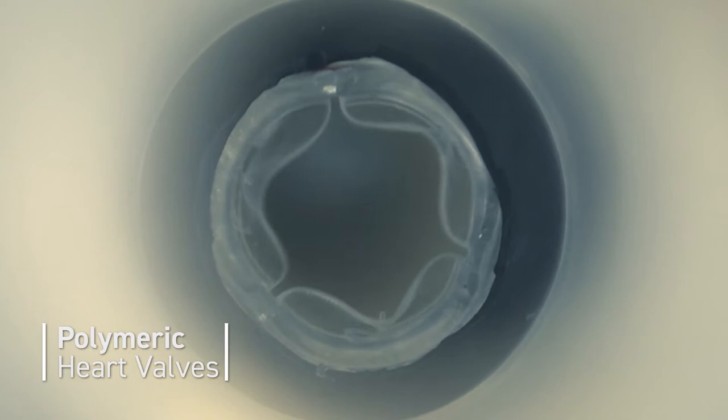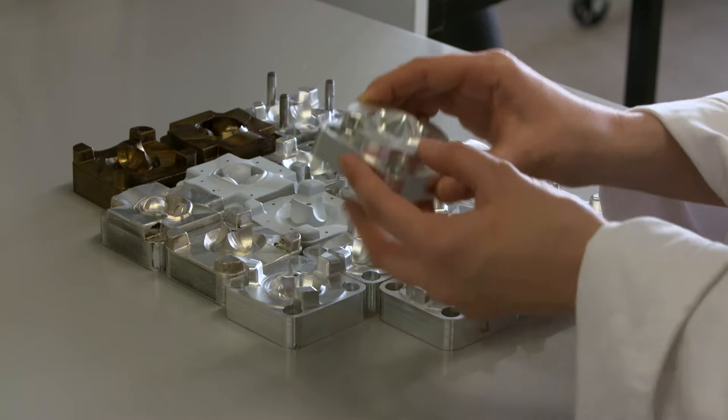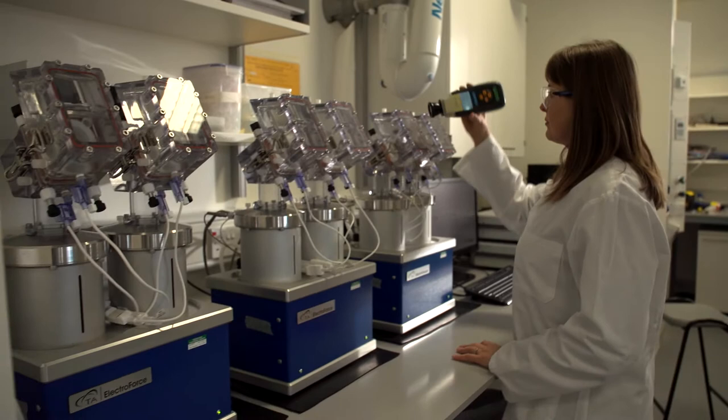So we're developing a polymeric aortic heart valve and the motivation behind it is because existing prostheses that are implanted suffer from having the need for anticoagulation medication, and that is associated with complications of risk of bleeding. So the advantage of a polymeric valve is that we don't need to take that medication.